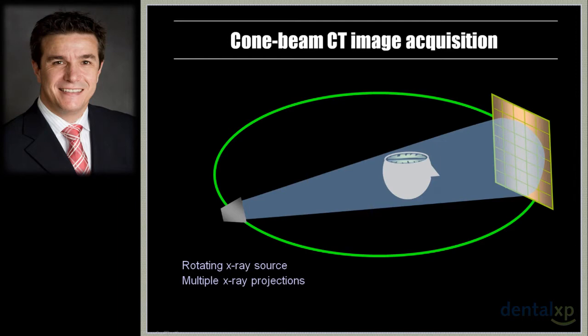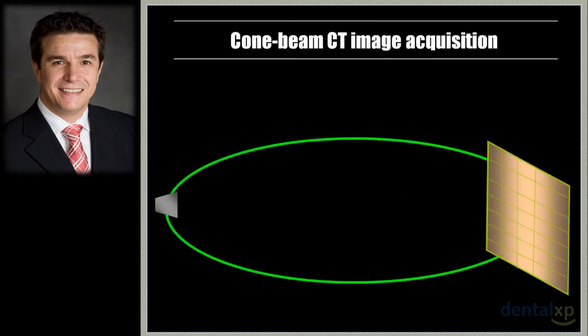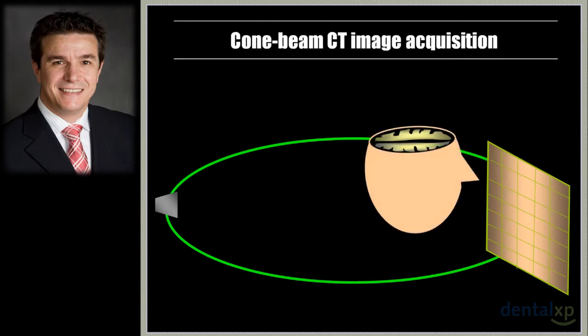of that cycle. Now all this X-ray attenuation data are collected continually by the detector and converted to an electrical signal, the intensity of which varies based on the X-ray energy that hit the detector, and as a result this variable X-ray energy will be converted to a variable shade of gray. If we look at it in a little more detail, we will realize that really the heart of the machine is the detector.